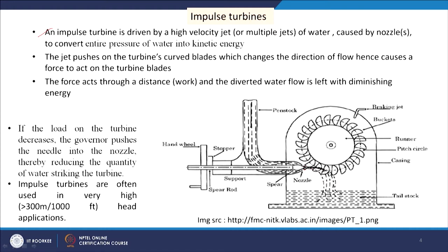The jet pushes on the turbine's curved blades, changing the direction of flow and causing a force to act on the blades. The water changes direction while the blades are forced to move, giving circulatory movement to the rotor. The diverted water flow is left with diminishing energy — the tailwater loses the energy available upstream. If the load on the turbine decreases, the governor reduces water flow by pushing the needle into the nozzle. Impulse turbines are often used in very high head applications.